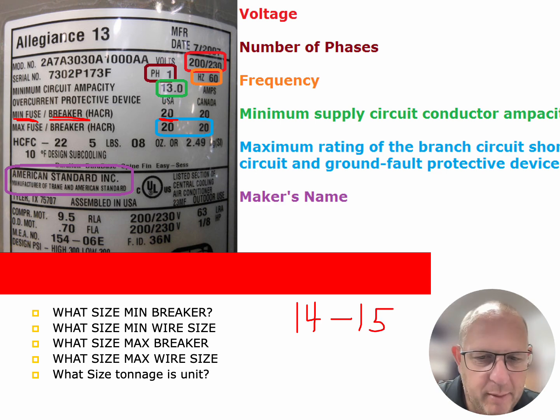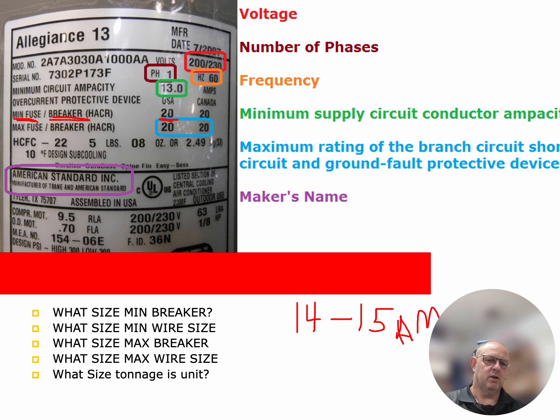And guys, these are minimum. If I was to get a breakdown of the actual wire that was running to this particular unit, you would see that a 14 gauge wire can actually, under certain circumstances, take more than 15 amps. But NEC code requires that a minimum circuit breaker be put on these particular wires so that they do not exceed a certain amperage on them. And that is found in the NEC book. 14 gauge wires, 15 amps. No more. Can't put any more than 15 amps on that particular wire. If we do that, that wire has the potential to burn up.